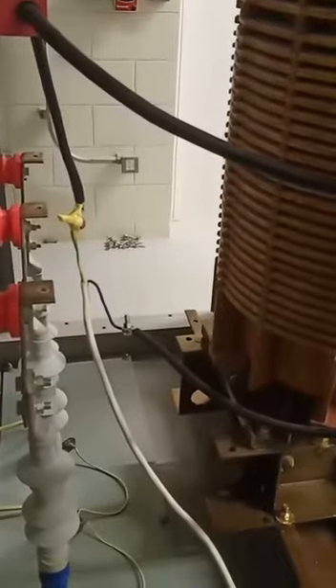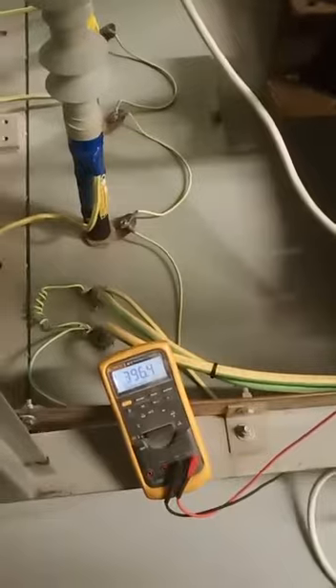This is the primary side of the transformer and the test voltage is 396.5 phase to phase, 396.5 we applied to primary side. Now we are going to check secondary side.